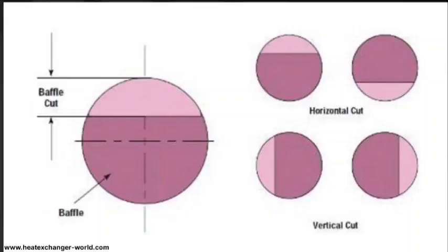Why did you not provide any baffle cut? Because without a baffle cut it is useless. In the thermal data sheet, TKI told us we don't need to provide any baffle cut, because they had put a baffle cut in revision 0. They commented that they don't require it and do not mention it in their data sheet. You have to provide it, and now they have denied accepting it.